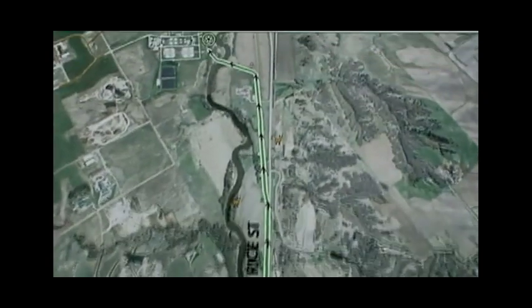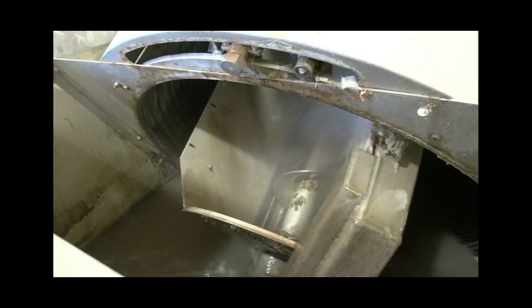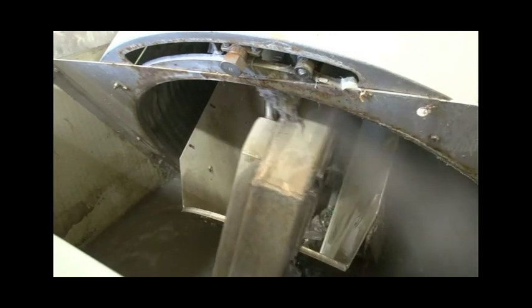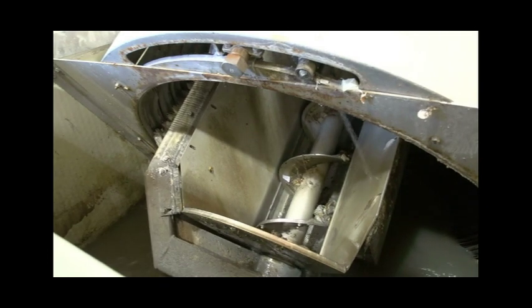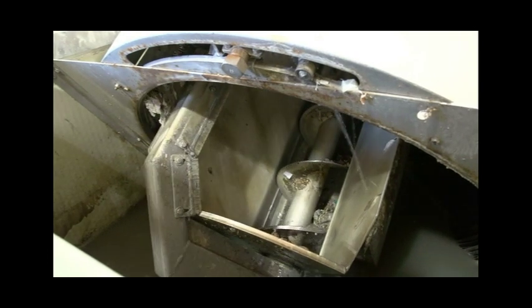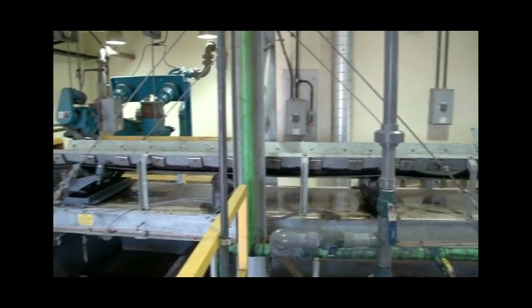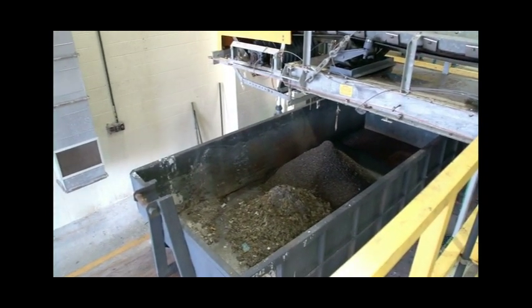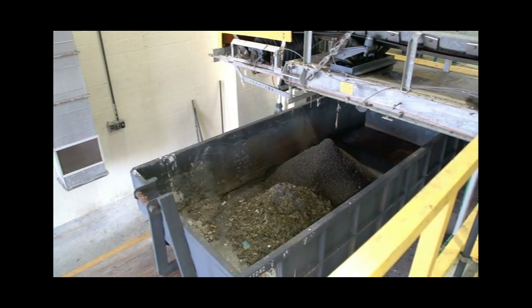The reclamation process begins with influent wastewater coming from the sanitary sewer lines and flowing into these screens. The influent flows through the quarter-inch circular bar screens to filter out the big stuff that inadvertently gets into the wastewater flow — stuff like rags, toys, and even false teeth. As debris collects on the screens and the water level starts to back up, the float on the right-hand side will turn the auger spray bar on and the rake teeth connected to that auger. This action cleans big items out of the screen, dropping them into an auger. A conveyor belt carries the debris away where it falls into a dumpster and is hauled away to a landfill.